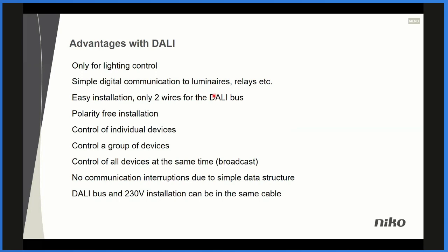The advantages that we have with DALI: it's only for lighting control, but it's a very simple digital communication to luminaires, relays, etc. It's a very easy installation. We only have 2 wires for the DALI bus, and it's a polarity-free installation. On this bus, we can control either individual devices, a group of devices, or you can control all devices at the same time. That's what we call a broadcast communication. Due to the simple structure of the data, there's no interruption of the DALI communication. That means that both the mains, the 240 volt, and the DALI bus can be in the same cable.